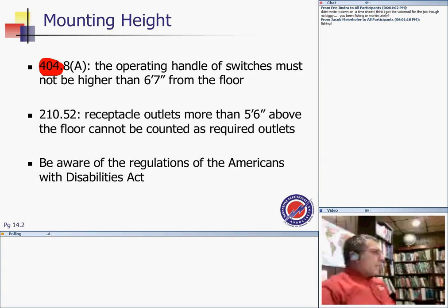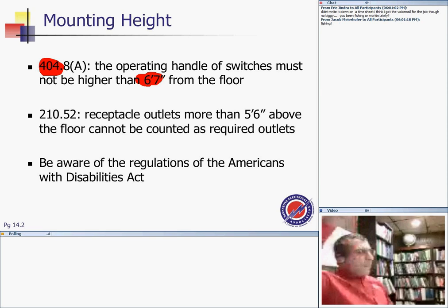What boxes should we be aware of? This article, guys, is about switches in particular. If you put a switch box, make sure the top handle of the switch is not above 6'7". For all switches, guys, for over 10 device switches, for snap switches, for 2-pole, 3-pole, any type of switch, from the top edge of the switch down to the floor, it cannot be more than 6'7". And that's directly for people like Chad who are short, so that you can extend your hand and push that thing to turn it on and off, or energize or de-energize the equipment if that's the goal of it. Okay. That's a height limitation on how far up you can put a box if it includes a switch.